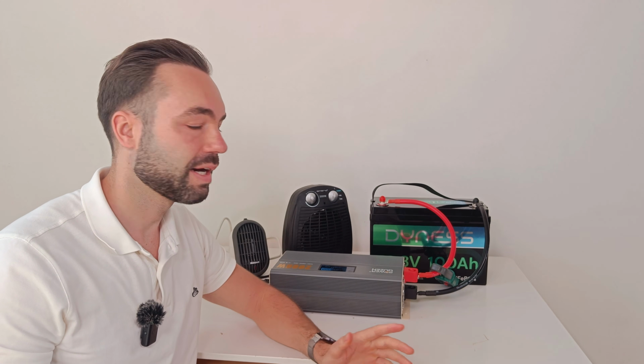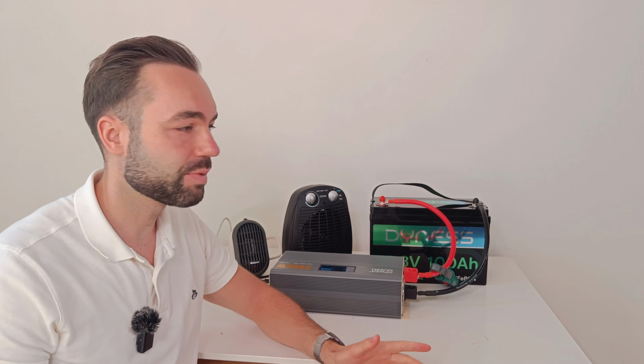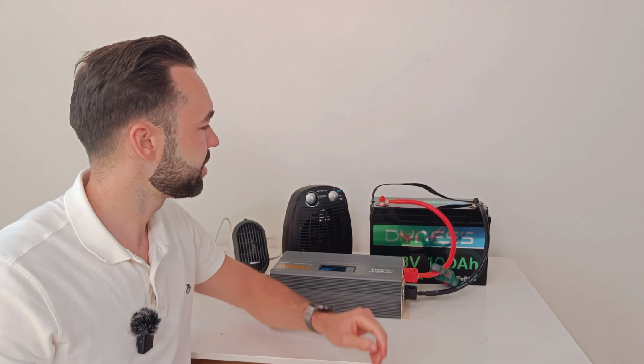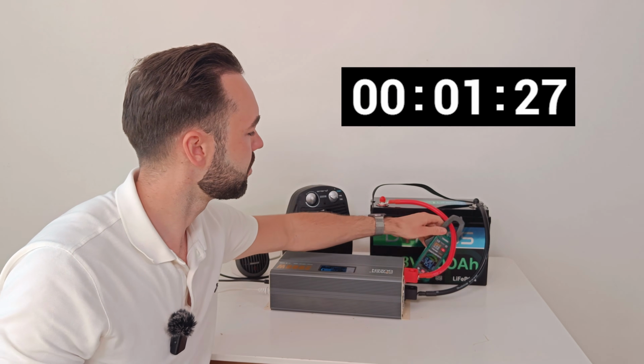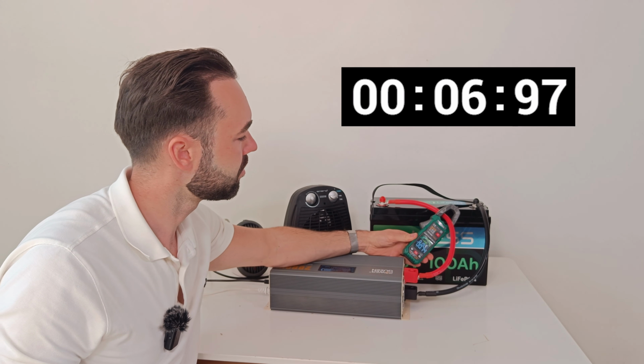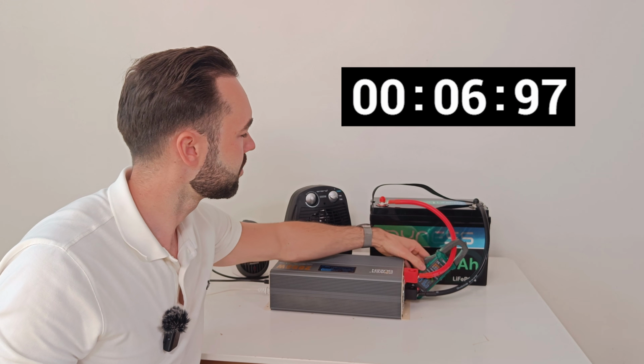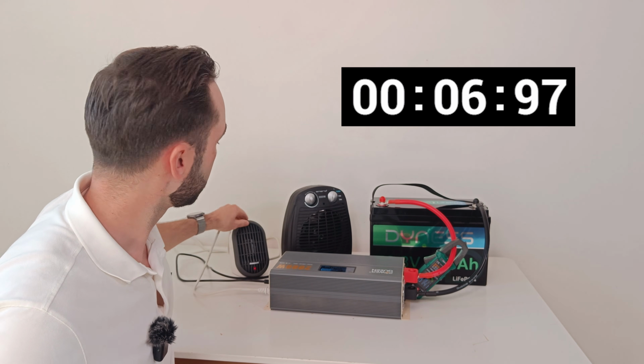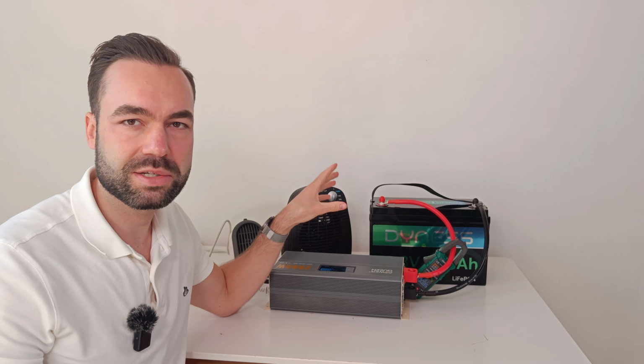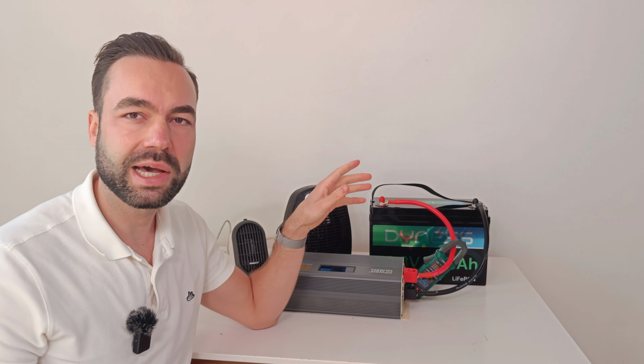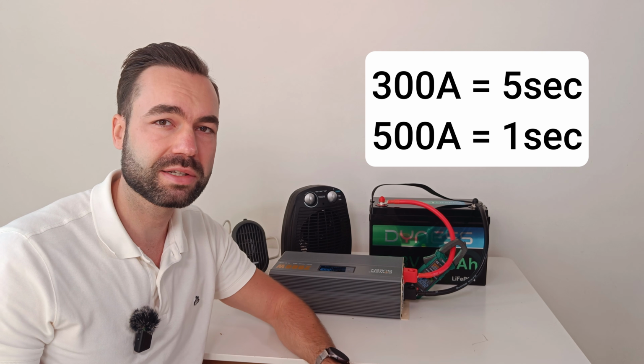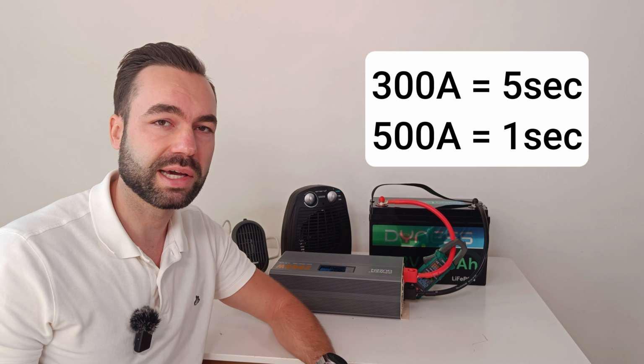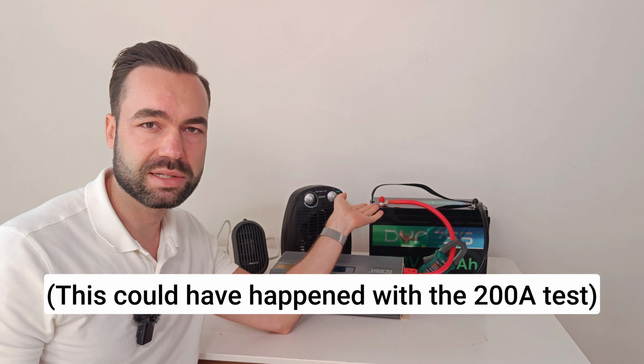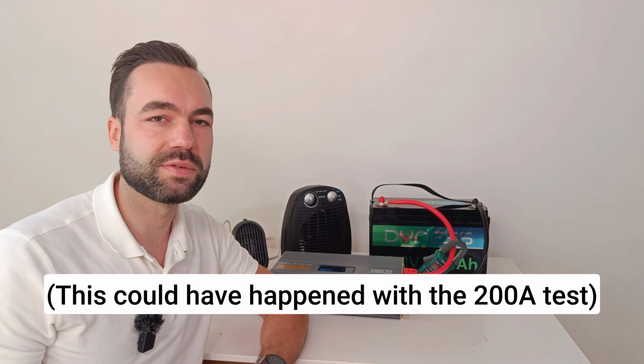So it didn't turn off at 160 amps, so let's now increase it to about 200 amps. And at 200 amps, the BMS turned off. So I emailed them and they told me the BMS can handle 300 amps for 5 seconds and 500 amps for 1 second. And it's also temperature dependent. So if the BMS inside gets too hot, it will shut itself off.